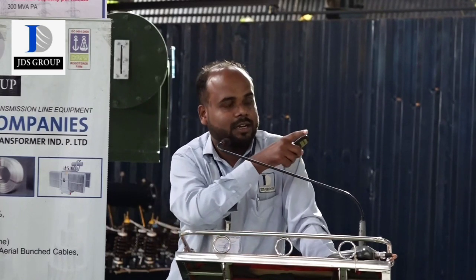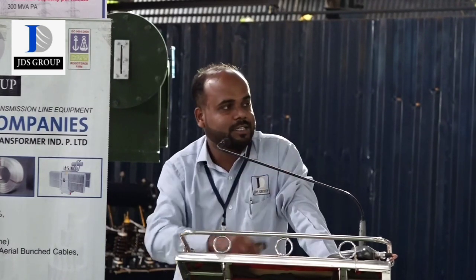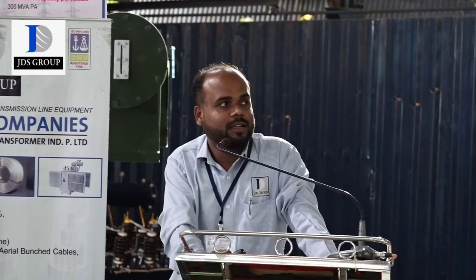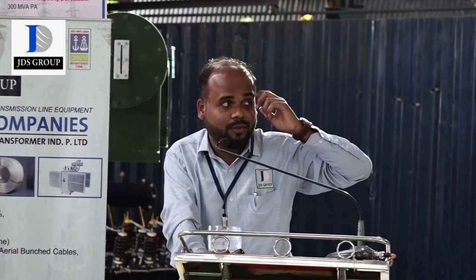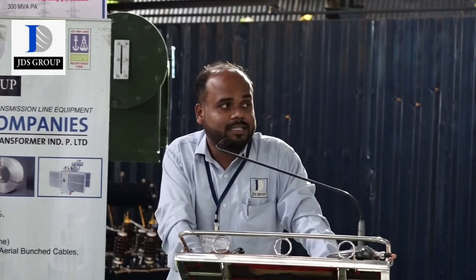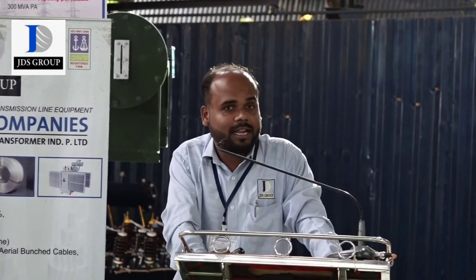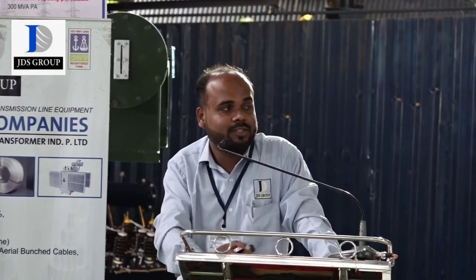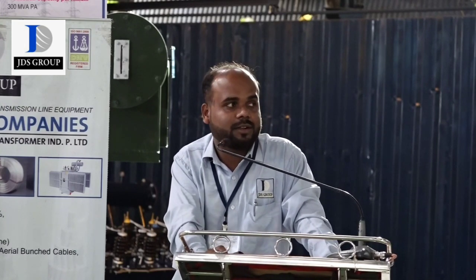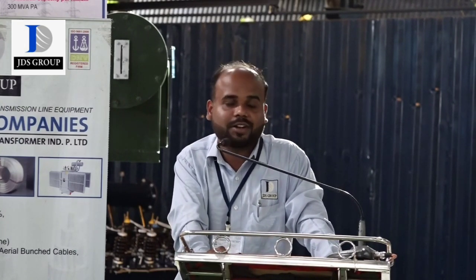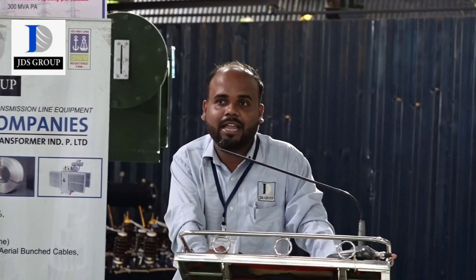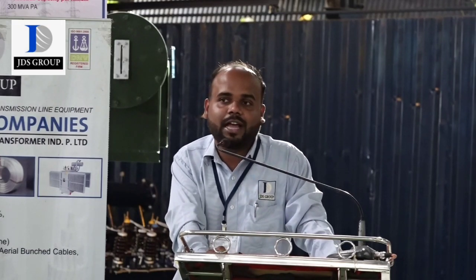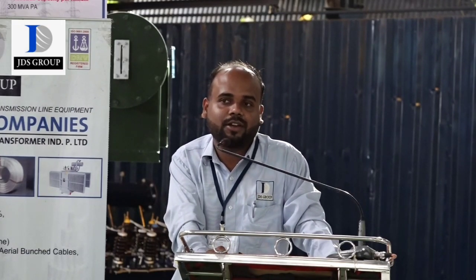So this is the representation of how many types of faults occur and what the reasons for the faults in the transformer are. Insulation plays a very major role, and it is correct that insulation is very important in a transformer, because if the insulation fails, our transformer will not be able to withstand any high voltage. At regular intervals we have to check the breaker of the transformer.